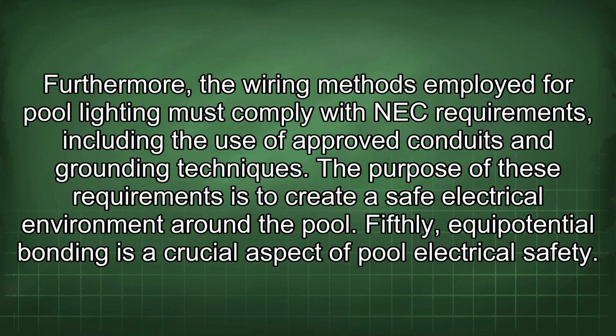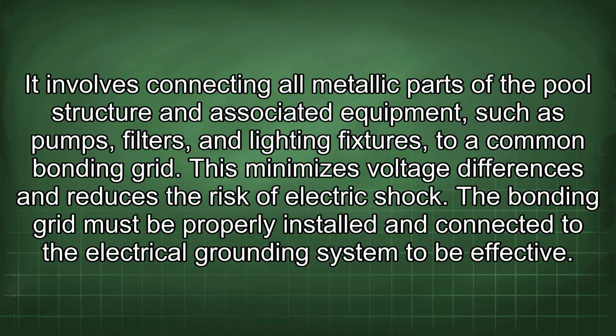Fifthly, equipotential bonding is a crucial aspect of pool electrical safety. It involves connecting all metallic parts of the pool structure and associated equipment, such as pumps, filters, and lighting fixtures, to a common bonding grid. This minimizes voltage differences and reduces the risk of electric shock. The bonding grid must be properly installed and connected to the electrical grounding system to be effective.